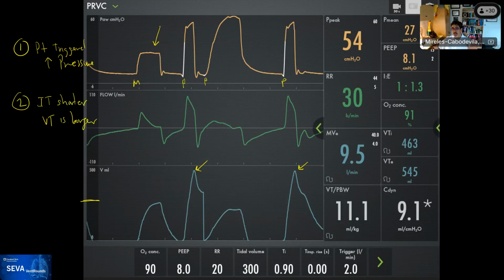So here comes the explanation of why this is happening. And this is reverse engineering in ways. So the reason why the first observation is that the patient triggered have higher pressure and the mandatory have lower pressure is because, and unless the Maquet engineers come and say otherwise, there's two adaptive algorithms occurring at the same time. One of the adaptive algorithms aiming at the tidal volume of 300 is for the mandatory breaths, so the machine trigger breath, sorry. And another algorithm is for the patient trigger breaths. So that if the patient triggers, they will get the pressure from an adaptive algorithm for patient trigger breath. So there's two algorithms going at the same time, one for the mandatory and one for the spontaneous breaths.